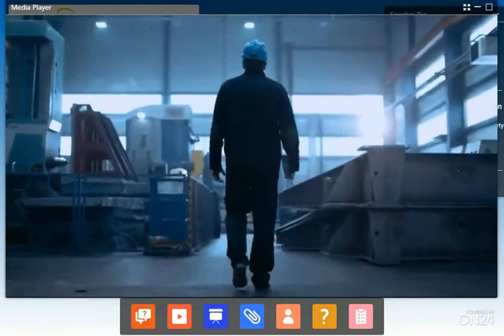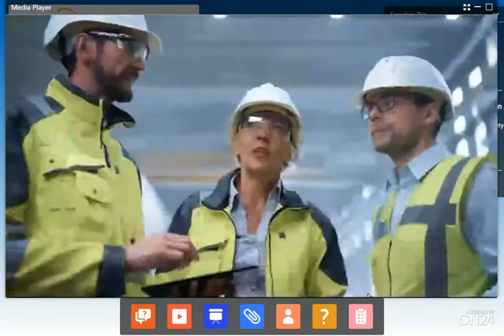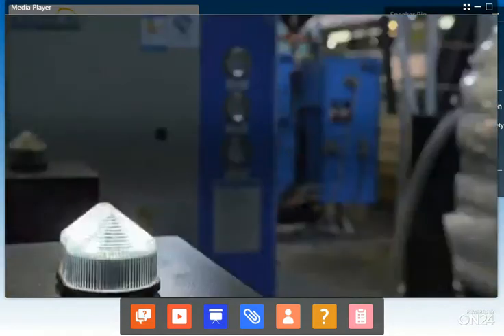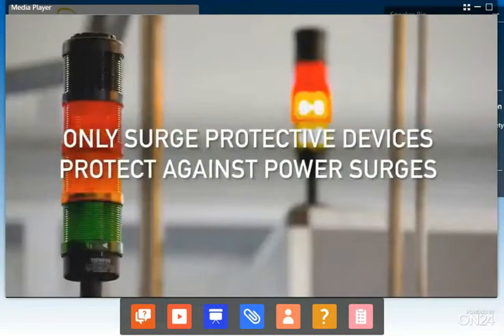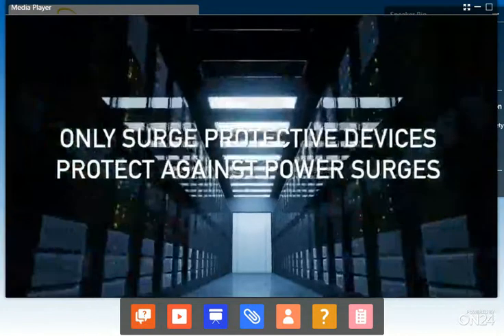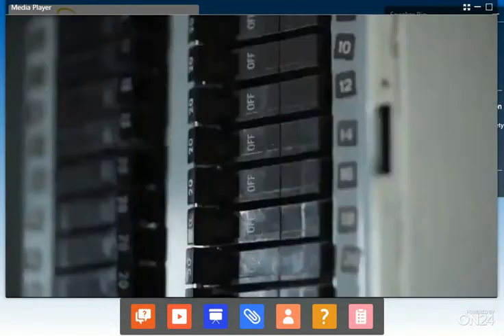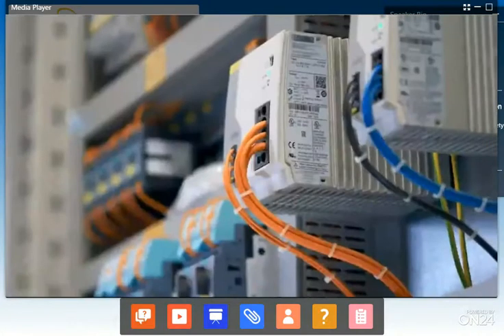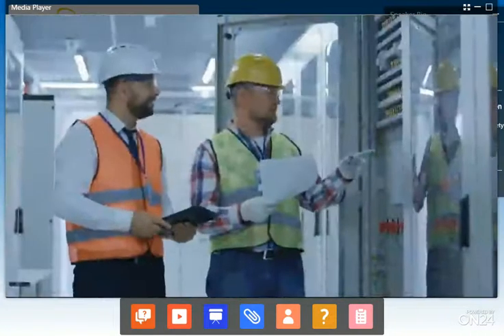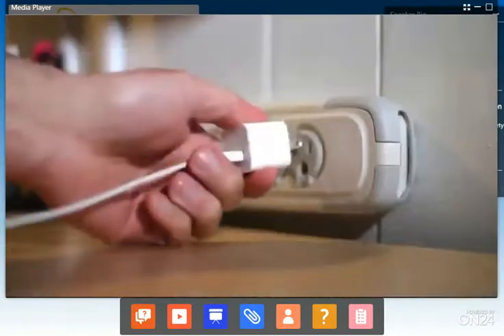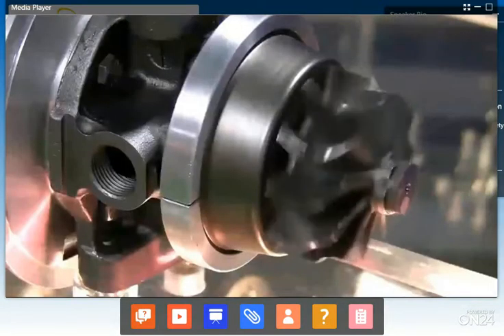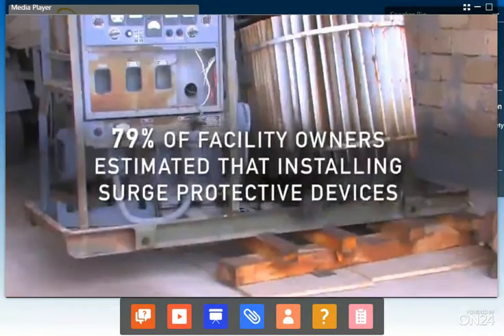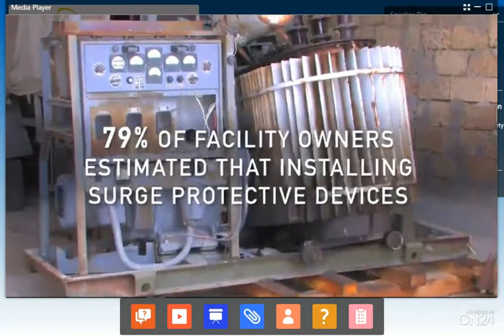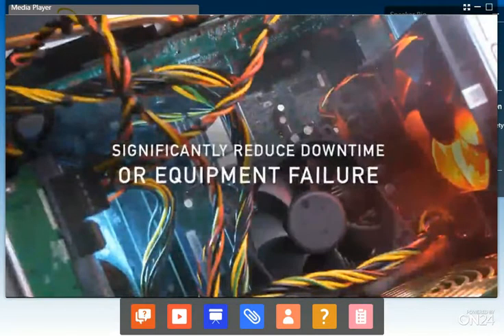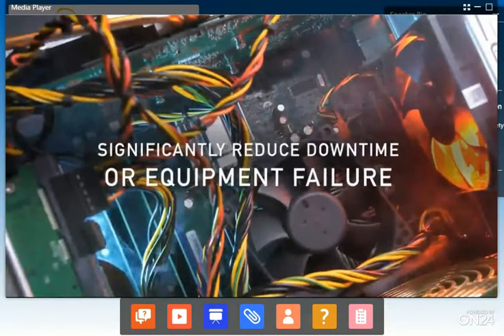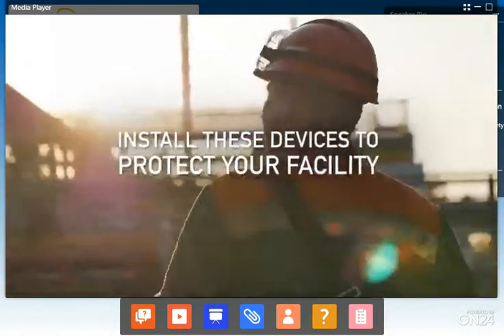A recent survey of facility professionals revealed mixed results on the knowledge of surge protection. Only surge protective devices, also known as transient voltage surge suppressors, protect against power surges. Fuses and breakers, GFCIs, wiring, low-cost uninterruptible power supplies, and typical power strips do not. A recent study found that 79% of facility owners estimated that installing surge protective devices would significantly reduce downtime or equipment failure. Install these devices to protect your...